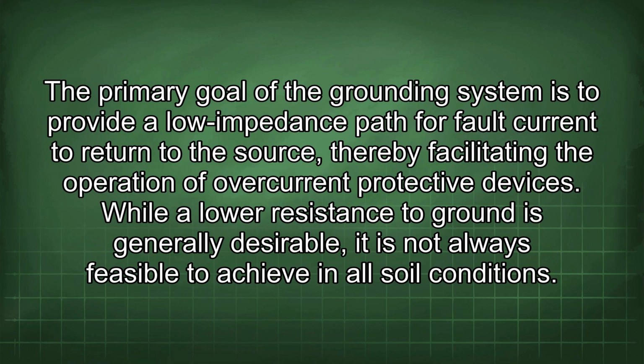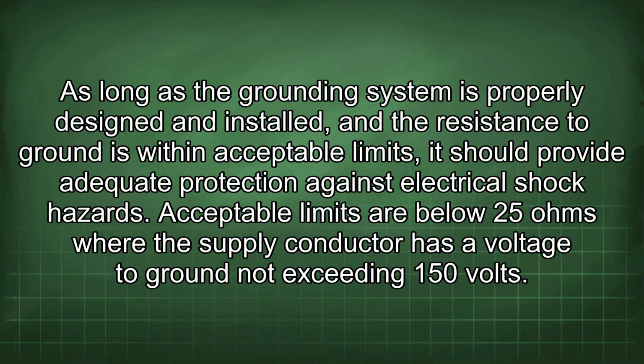The primary goal of the grounding system is to provide a low impedance path for fault current to return to the source, thereby facilitating the operation of overcurrent protective devices. While a lower resistance to ground is generally desirable, it is not always feasible to achieve in all soil conditions. As long as the grounding system is properly designed and installed, and the resistance to ground is within acceptable limits, it should provide adequate protection against electrical shock hazards. Acceptable limits are below 25 ohms where the supply conductor has a voltage to ground not exceeding 150 volts.